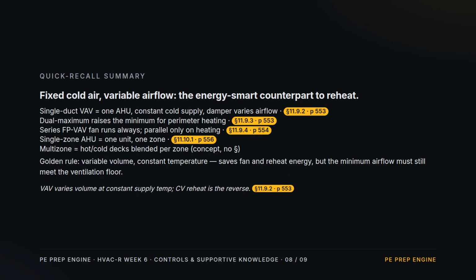Quick recall. Single duct VAV is one air handler with a constant cold supply, and a damper at each zone that varies the airflow. Dual maximum raises the minimum for perimeter heating. Series fan-powered runs its fan always, parallel only on heating. The single zone unit serves one zone, and multi-zone blends hot and cold decks per zone as a concept. Golden rule, variable volume, constant temperature. It saves fan and reheat energy, but the minimum airflow must still meet the ventilation floor.